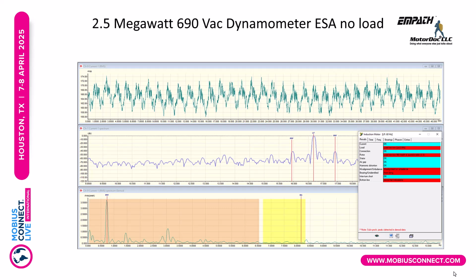And you can see that oscillating current on top. So we knew right away we had some kind of rotor bar issue in the machine. And you can see the pole pass frequency peaks there, and we're at about -40. It is a copper rotor bar machine, so that actually means I have fractured bars.